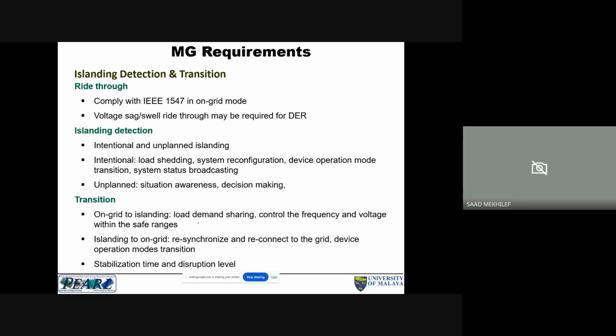From islanding to grid, we have to worry about resynchronization and the reconnection device. In both cases, either on-grid to islanding or islanding to on-grid, we need to make sure it is done within an acceptable time frame. We're talking about one to two cycles, not more than that. One cycle is 20 milliseconds for 50 hertz, so 20 to 40 milliseconds as a maximum. So it has to be fast.